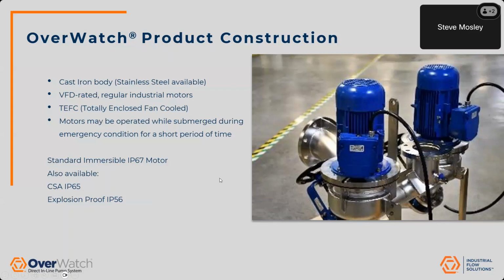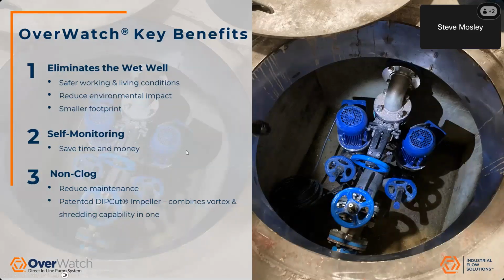The standard motors that we use are the IP67 design, which are immersible for short periods of time. We also have additional motors available, whether if you need an FM explosion-proof motor, we've got options there. And we've got CSA motors, which are suitable for use in Canada. Many of those have different IP ratings, and we would make sure to call that out as needed for the different motor approvals.